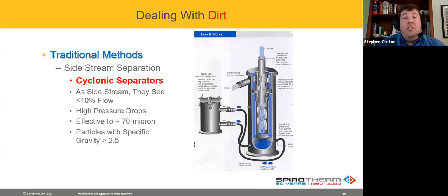Another type you see is the cyclonic separator. It spins and uses centrifugal force. Typically, you're looking at around 70 to 75 microns, with a specific gravity of 2.5 or greater, unless you go with a separate solids recovery vessel, which is basically a bag filter. Oftentimes, those come with a separate pump on a side stream, so you're only seeing part of the flow, part of the time. So that's one way it's been dealt with in the industry.